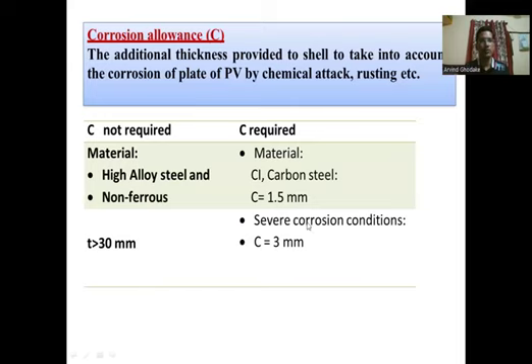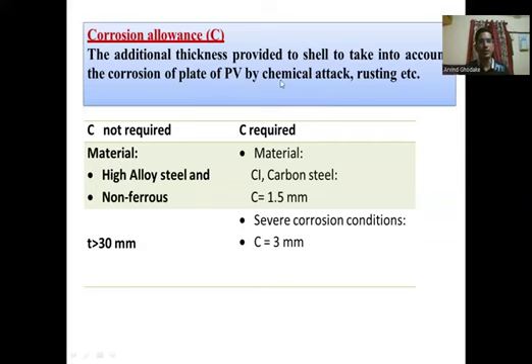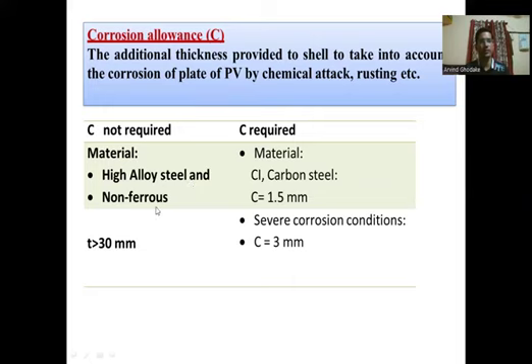The next term is corrosion allowance — the additional thickness provided to the shell to account for corrosion of the pressure vessel plate due to chemical attack or rusting. This additional thickness is denoted by C. For high alloy steel and non-ferrous materials (with no or very little carbon), no corrosion allowance is required.